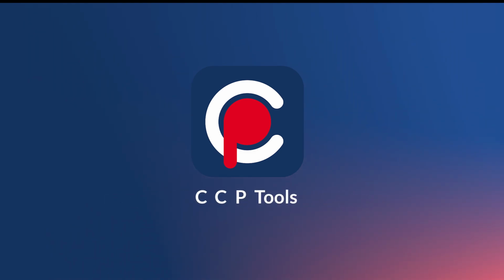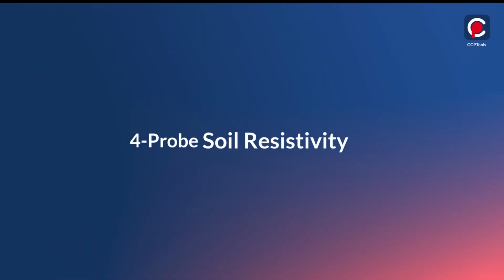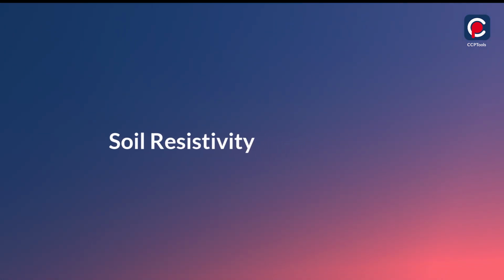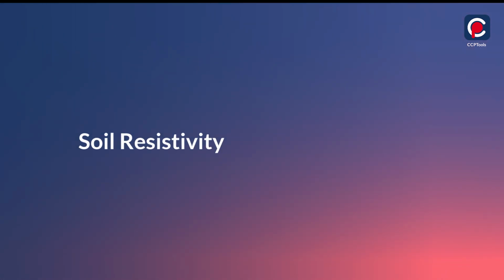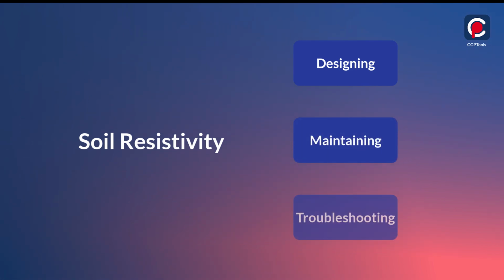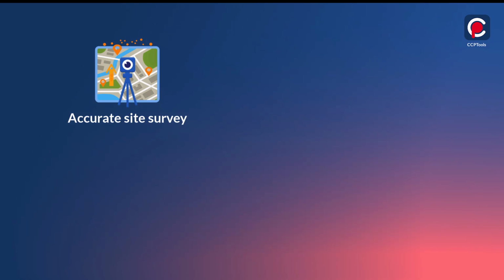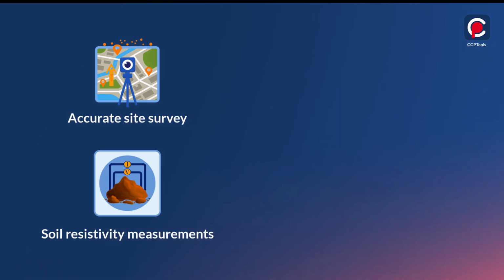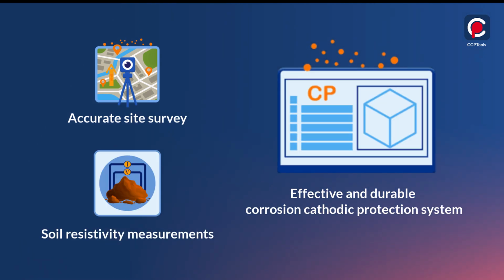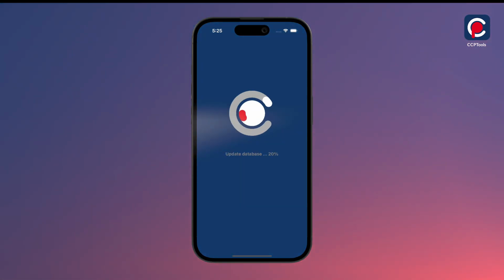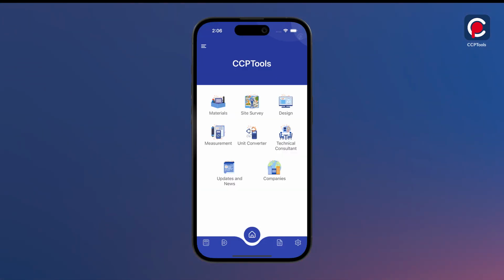Welcome to CCP Tools. This video explains the procedure for calculating 4-pin or 4-probe soil resistivity using CCP Tools. Soil resistivity is a crucial aspect of site surveys for designing, maintaining, and troubleshooting cathodic protection systems. A more accurate site survey, including soil resistivity measurements, can result in a more effective and durable cathodic corrosion protection system. To initiate the process, first launch the CCP Tools mobile application.